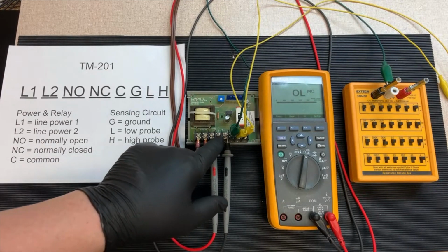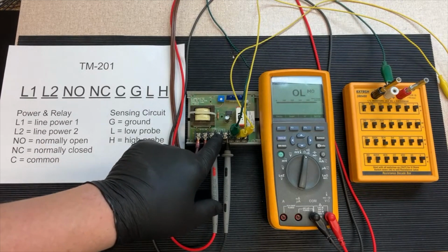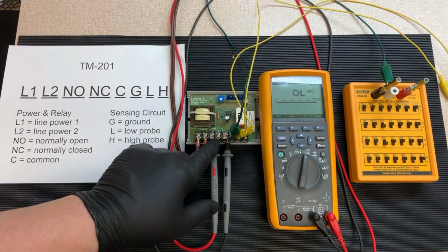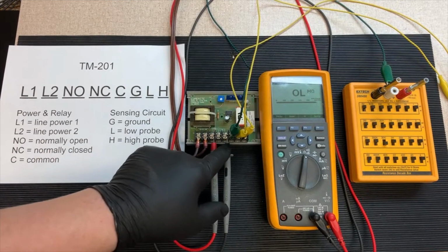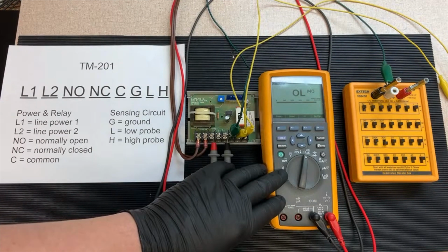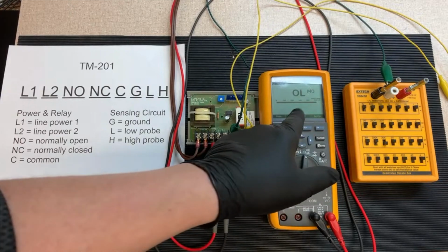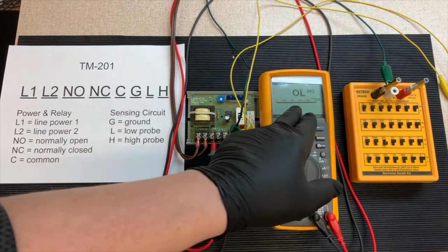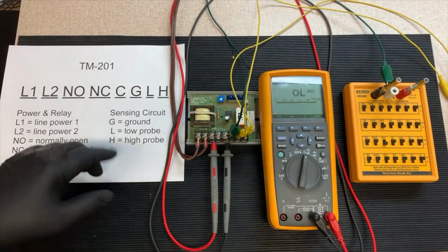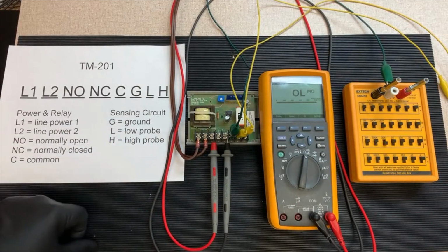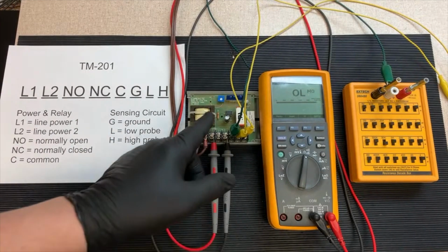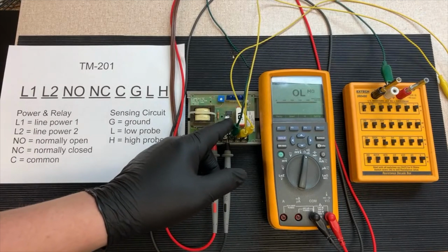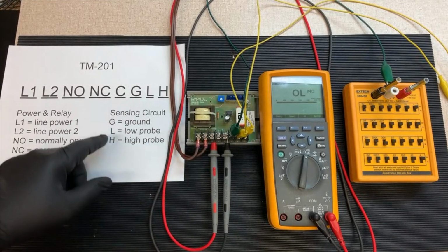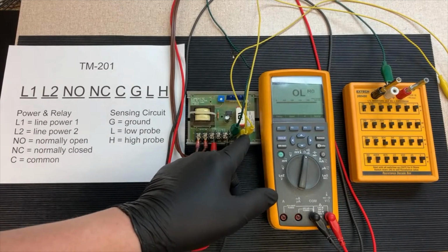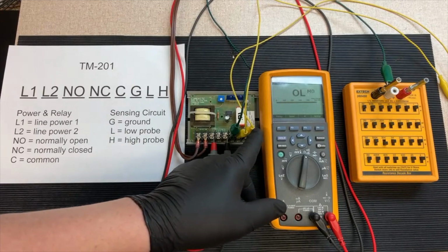This is normally open. Normally closed has nothing on it right now because we're just testing for switch closure on normally open. And then common is right off here. We're hooked up to the ohm meter right now, obviously, since the relay is de-energized, we're getting an OL on the display. Then we move on to the sensing circuit. We have the ground, which I put the green alligator clip on. And then the low and the high are just the two yellow, low, and then high is on the right-hand side all the way at the end.